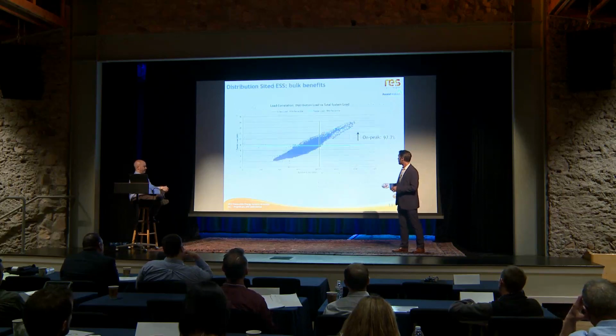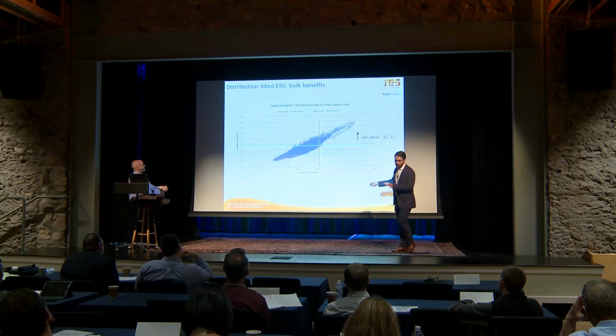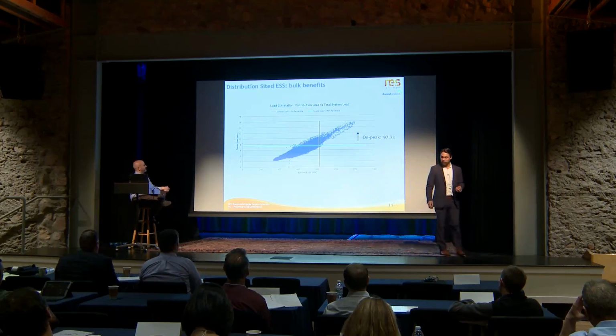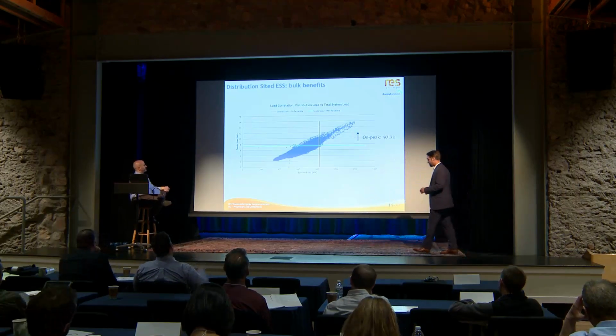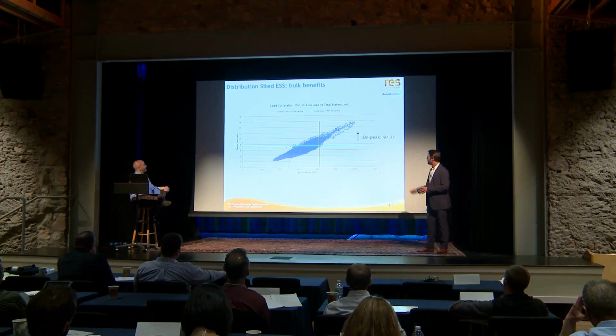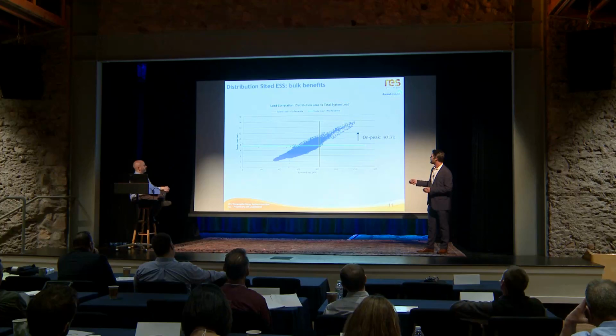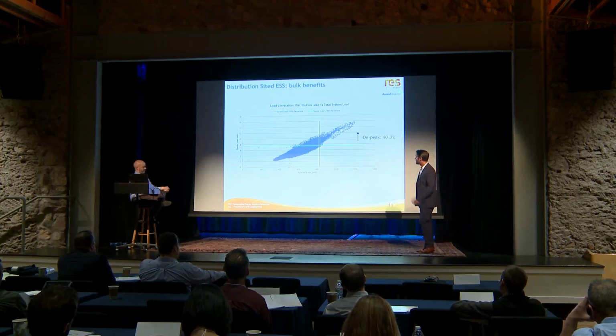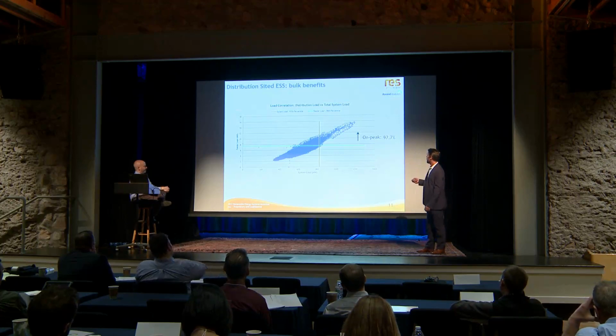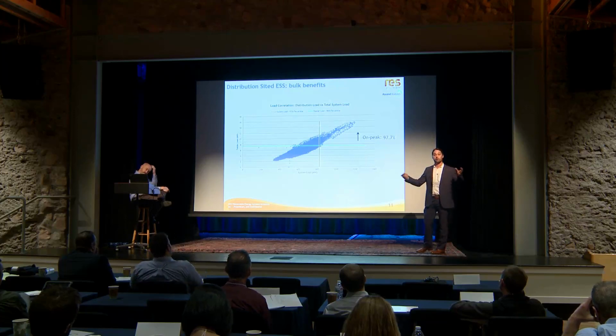Now I want to show you a nuance we discovered while working on this. What you see here is a load correlation of the distribution load, the feeder load on the y-axis versus the system load. I've drawn lines at feeder load over the 90th percentile and system load over the 97th percentile to show when both systems are peaking at the same time.